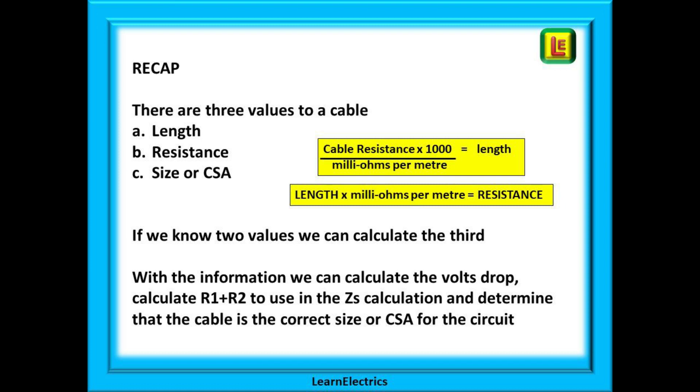With all the information that we now have that relates to the cable we can do a number of things. We can calculate the volts drop in the cable. In other words how much voltage is lost in the copper conductors. We can calculate R1 plus R2, the resistance of the cable. And this can be used in our ZS calculations later on. Also we can determine that the cable is the correct size for safety and economy.